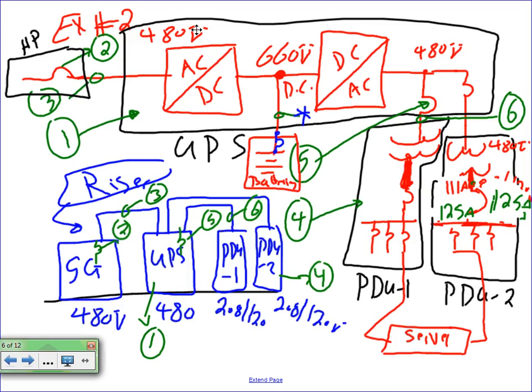So what is a UPS? A UPS, guys, you take your AC, in this case 480, and convert it to DC, close to 660 volt. So this is 660 volt DC coming from a 480. This is where you have the conversion to DC. At the DC level, they are tied to batteries. You can see these are batteries. Right here is a bank of batteries.